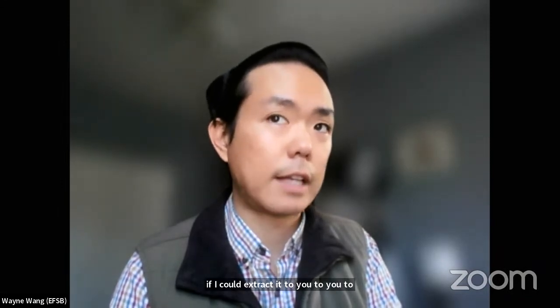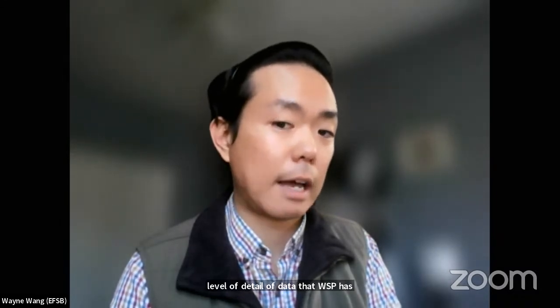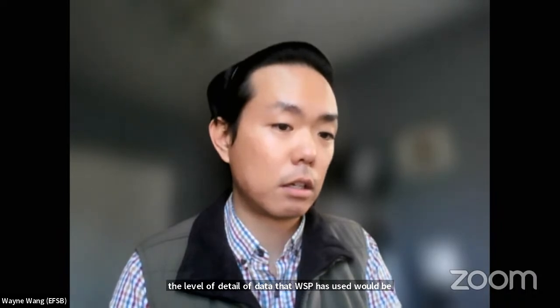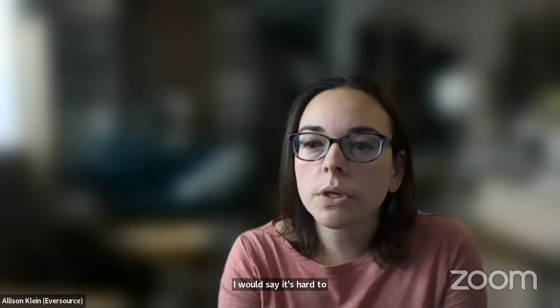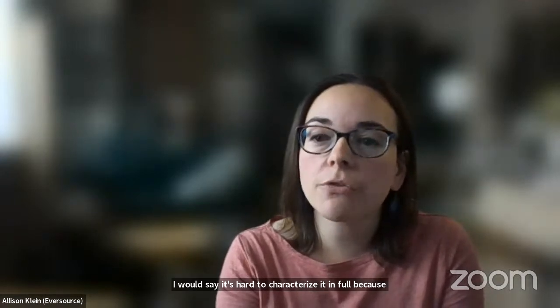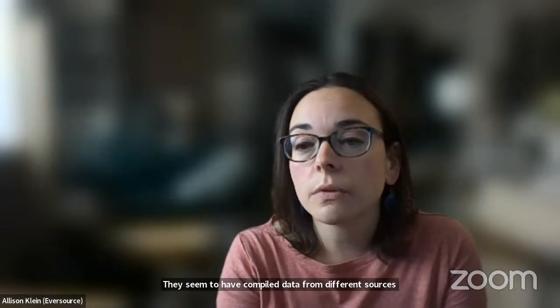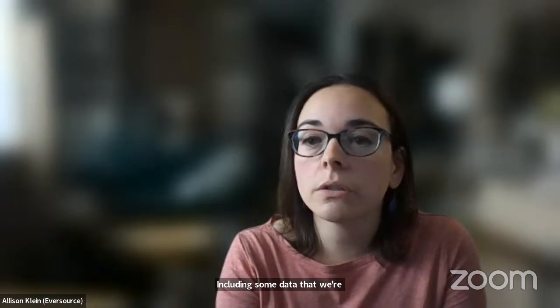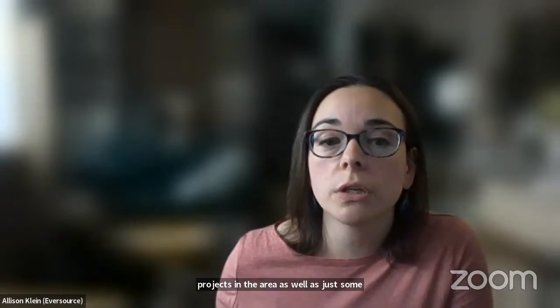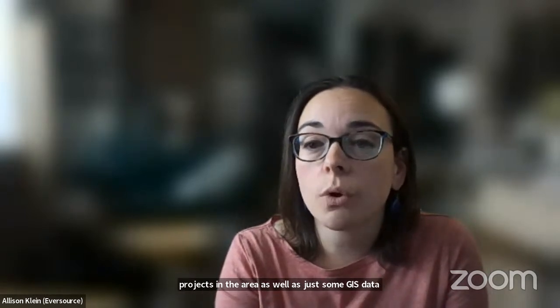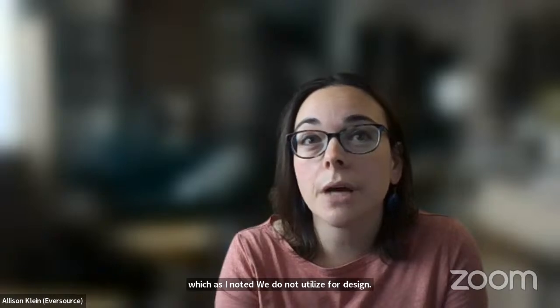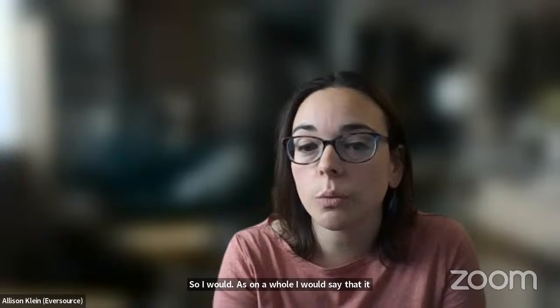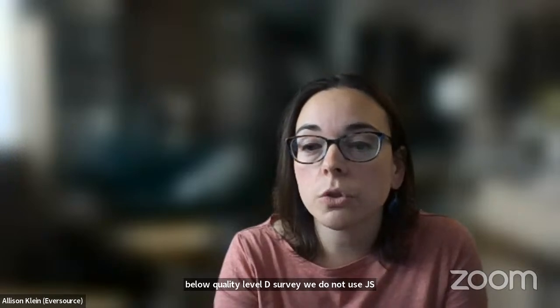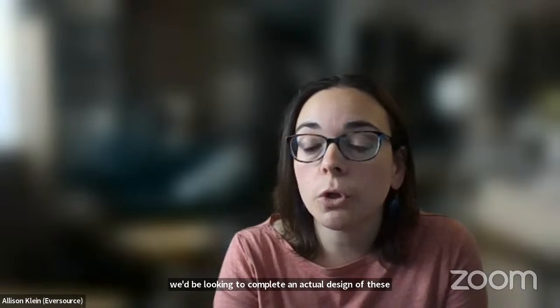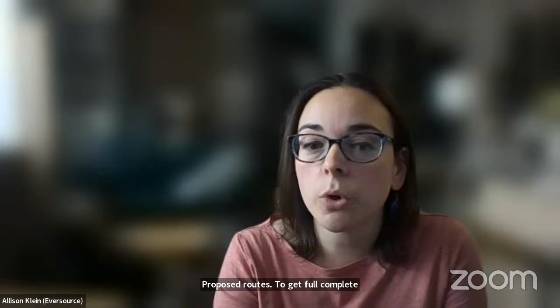And if I could extrapolate, do you see that the level of detail of data that WSP has used would be level D, or is that below level D? I would say it's hard to characterize it in full because they seem to have compiled data from different sources, including some data that were acquired from other projects in the area, as well as just some GIS data, which, as I noted, we do not utilize for design. So I would say that it's below quality level D survey. We do not use GIS data, and we'd be looking to complete an actual design of these proposed routes to get full, complete, updated survey from start to end point. Okay.